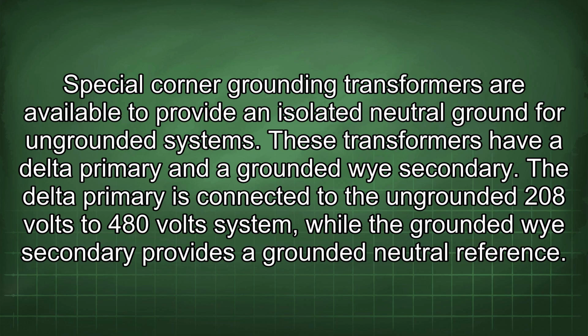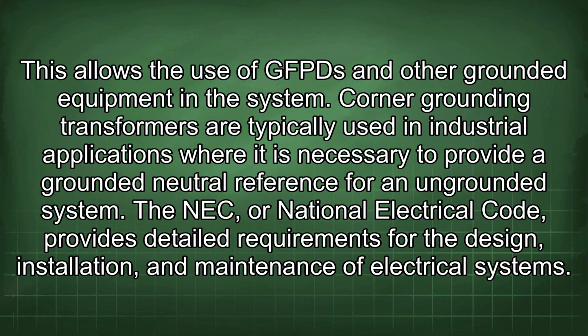Special corner grounding transformers are available to provide an isolated neutral ground for ungrounded systems. These transformers have a delta primary and a grounded Y secondary. The delta primary is connected to the ungrounded 208 volts to 480 volts system, while the grounded Y secondary provides a grounded neutral reference. This allows the use of GFPDs and other grounded equipment in the system. Corner grounding transformers are typically used in industrial applications where it is necessary to provide a grounded neutral reference for an ungrounded system.